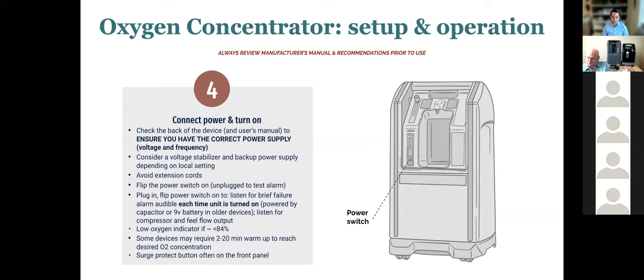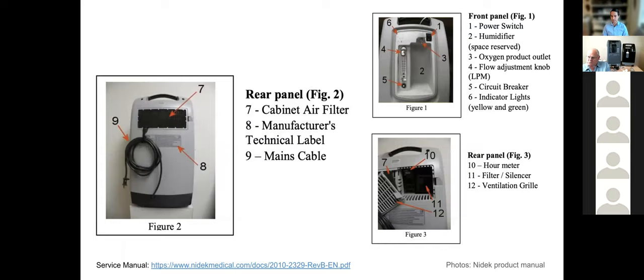Most devices should have a low oxygen indicator light, an alarm, which will go off if the concentration of oxygen coming out of the unit is less than 84%. One thing to note is some devices do have a warm-up period of anywhere from 2 to 20 minutes to reach the desired oxygen concentration. And then finally, the surge protect button in the Nidek model, we showed it on the front panel here, number 5 in the top right. If there is a surge, that button may need to be pressed.